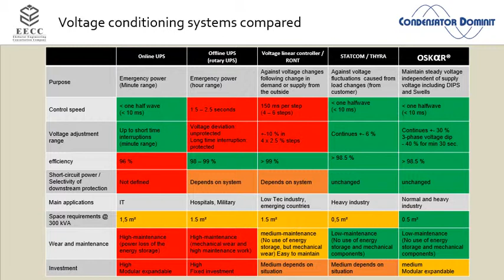That is theoretically possible. It works in plenty of applications, but according to my practical experience, all the cases wherever somebody tried to run a factory behind a UPS system, it failed. A UPS system, especially an online but also an offline UPS system, has one big disadvantage: the short circuit power goes down dramatically.